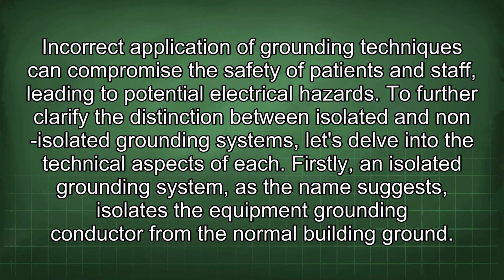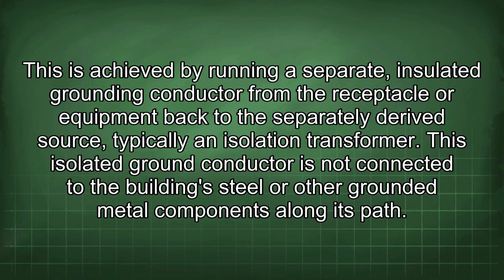To further clarify the distinction between isolated and non-isolated grounding systems, let's delve into the technical aspects of each. Firstly, an isolated grounding system, as the name suggests, isolates the equipment grounding conductor from the normal building ground. This is achieved by running a separate, insulated grounding conductor from the receptacle or equipment back to the separately derived source, typically an isolation transformer. This isolated ground conductor is not connected to the building's steel or other grounded metal components along its path.